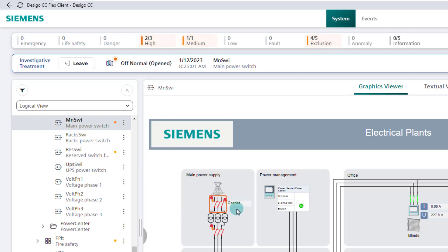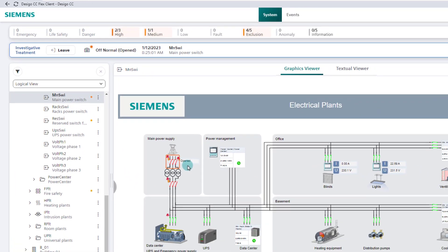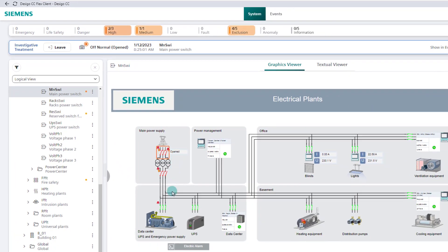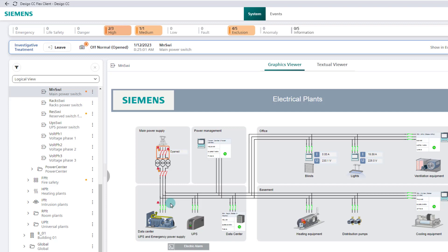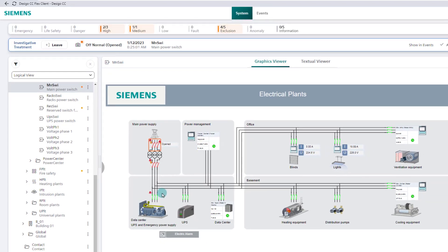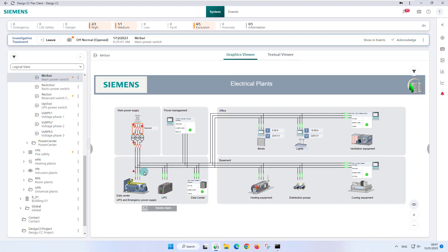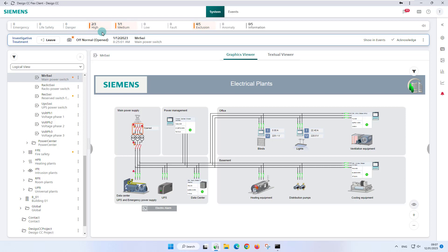As seen here with our example. As a result of the open main switch of the main electrical supply, a fault has also occurred in the uninterruptible power supply. The main power switch object is a high alarm category and the summary bar shows us two unprocessed events as high alarm and three events in total.